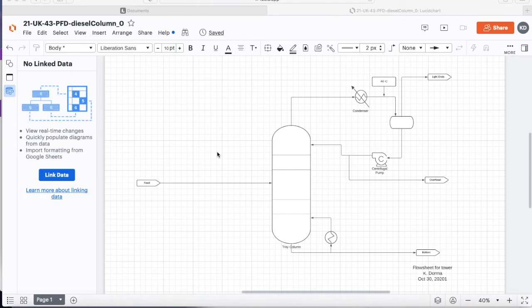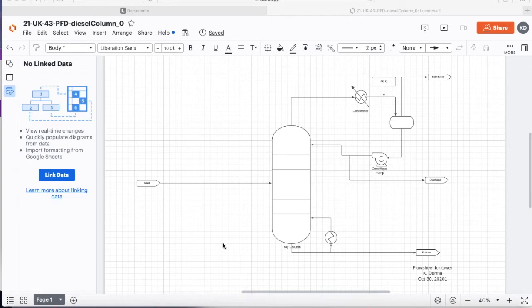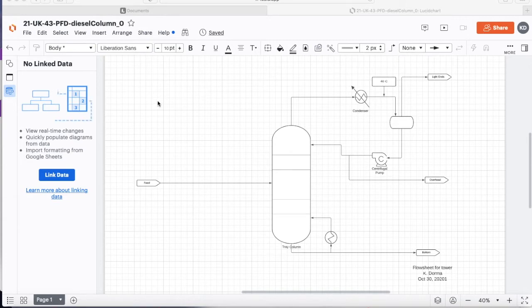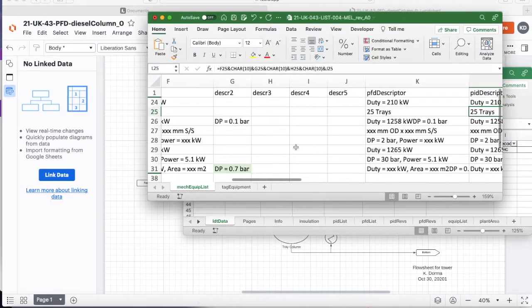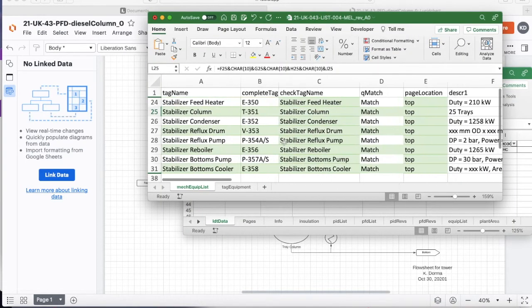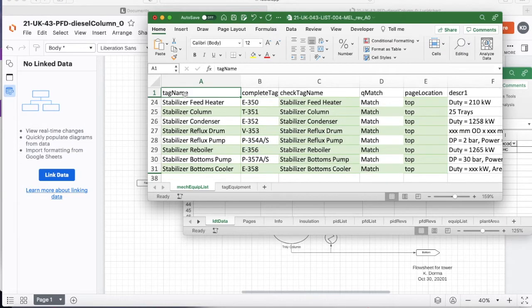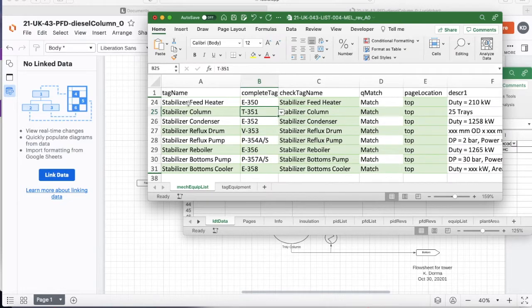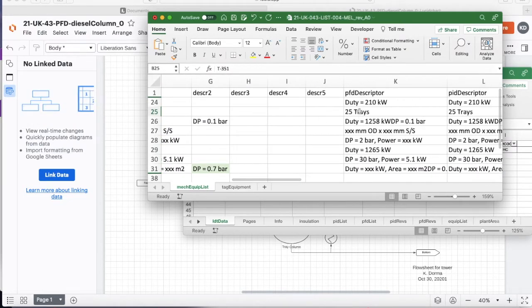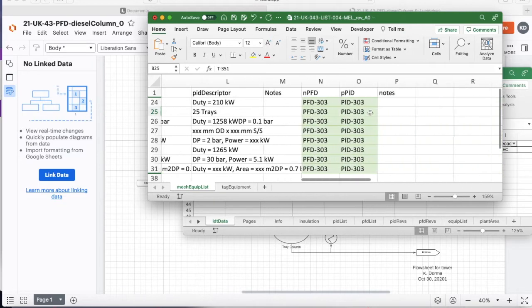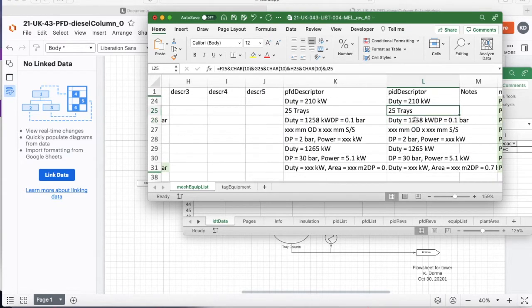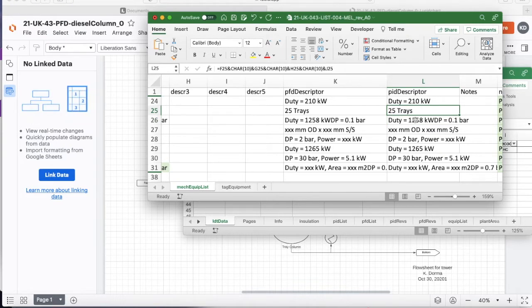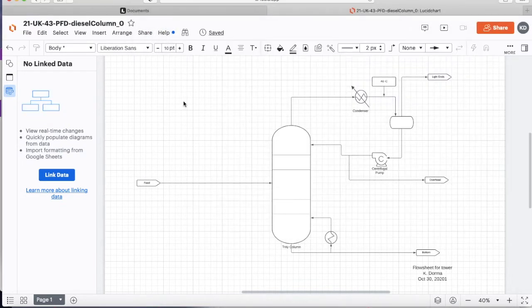We're going to start with the equipment list. Now typically the list of equipment will be at the top or maybe the bottom if it's pumps, and it will contain the equipment tag number, the equipment name, and some useful information for the pump or for the equipment. Now my equipment details are in a spreadsheet. The sheet is called MEL, this is the mechanical equipment list, and I've got a bunch of information for all this equipment. So if it's the distillation column, it's got a tag, it's got a name, and for this P&ID I've got some descriptor for it that I will have on the drawing. So the question is how do I get this data on this spreadsheet into this drawing?